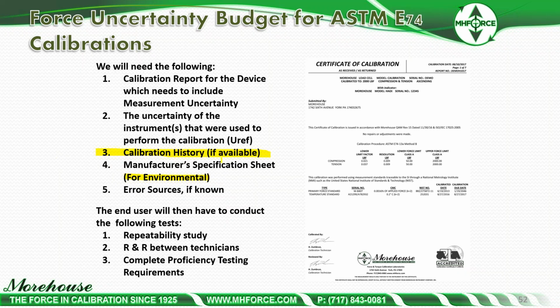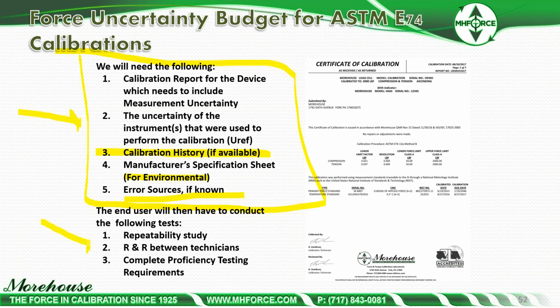End user, so that we get asked this: can you do an uncertainty budget for me? Yes and no. We can pull most of this for anything, right? Error sources, we're going to have to ask a lot of questions. But in the end, the user will always have to conduct their own repeatability study. They will always have to check the repeatability and reproducibility between their technicians. And you're going to have to complete some type of proficiency testing requirements, which wraps it all together.